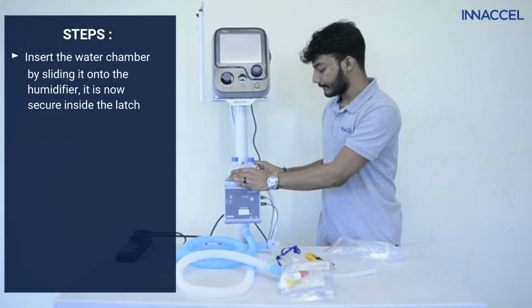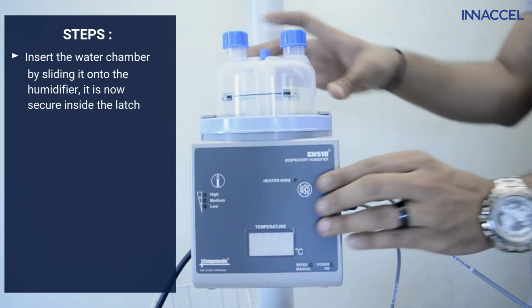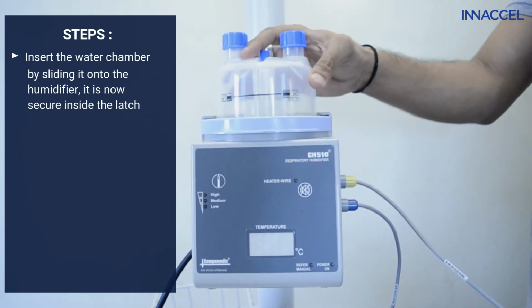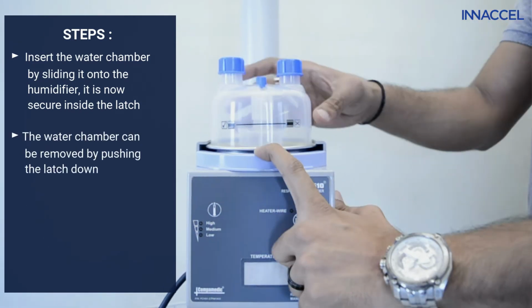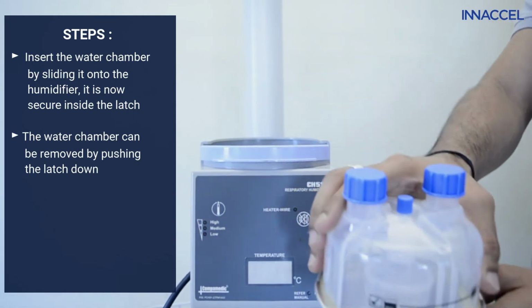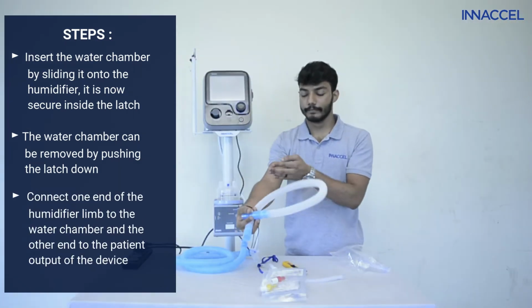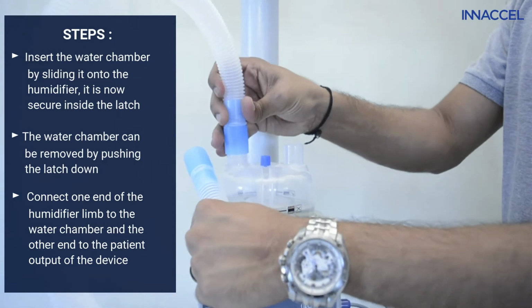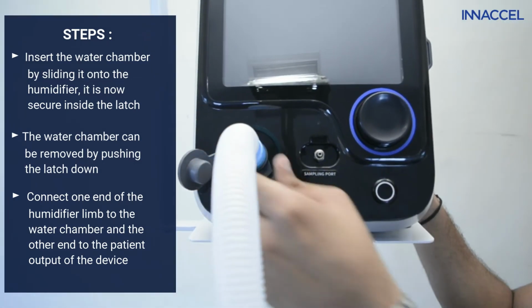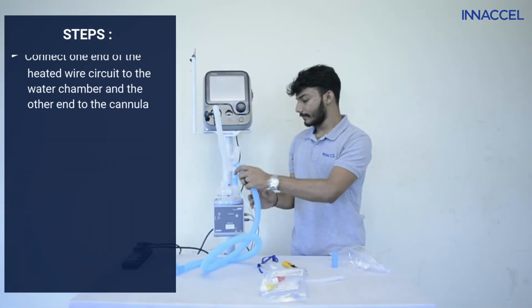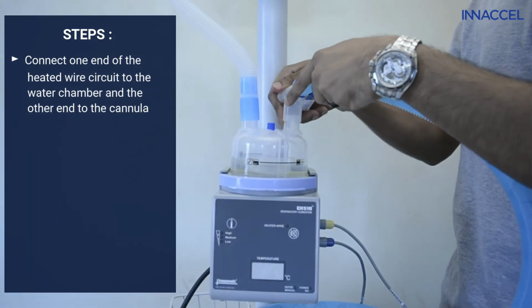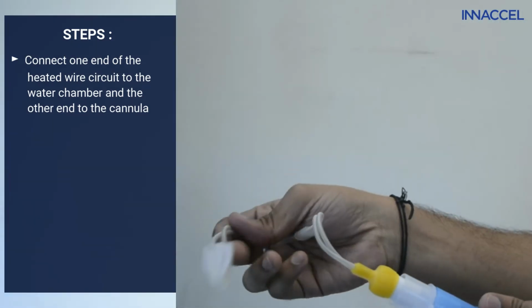Insert the water chamber by sliding it onto the humidifier. It is now secure inside the latch. The water chamber can be removed by pushing the latch down. Connect one end of the humidifier limb to the water chamber and the other to the patient output of the device. Connect one end of the heated wire circuit to the water chamber and the other end to the cannula.